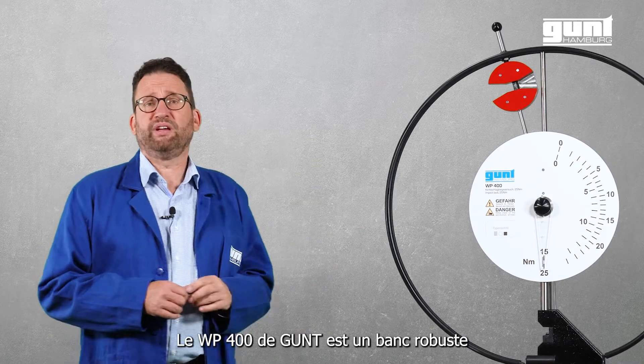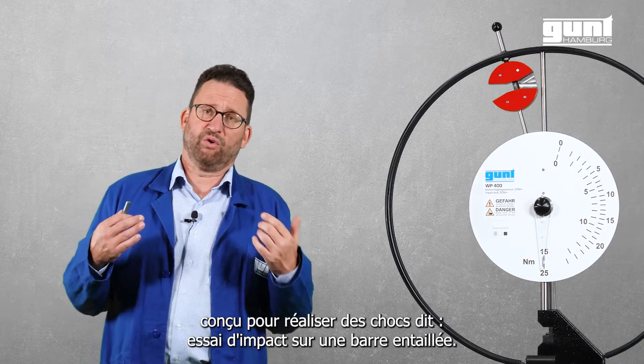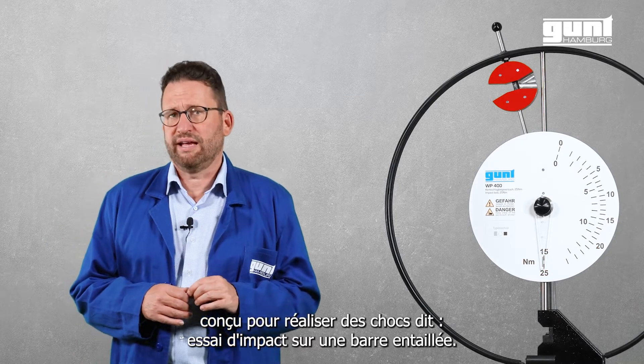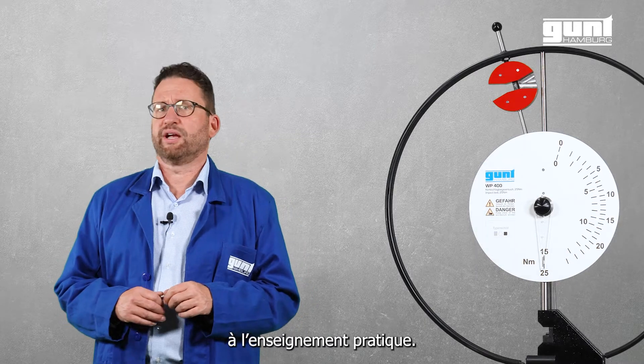The GUNT WP400 is a solid pendulum impact tester designed to perform the so-called Charpy Notched Bar Impact Test. The clean layout and its simple operation make it perfectly suitable for your teaching environment.